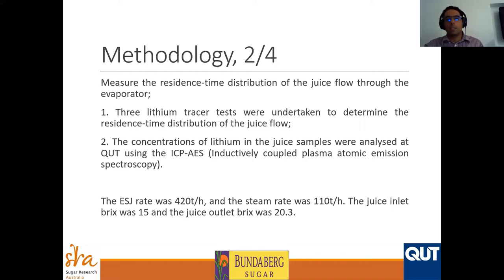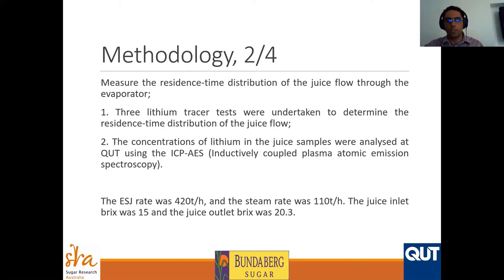Second, we performed residence time distribution measurements using a lithium tracer test — an industry-standard method. One kilogram of lithium chloride was mixed with ESJ, injected into a pressurized vessel, and then injected into the incoming ESJ feed to the evaporator. Samples were collected at three different times — two in August, one in October — and sent to the lab to determine lithium concentration. We tried to keep working conditions consistent: ESJ rate at approximately 420 tonnes/hr, steam rate at 110 tonnes/hr, inlet brix at 15 and juice outlet brix at 20.3.